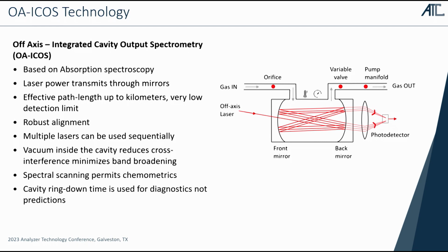We make these measurements at reduced pressure. We bring in low pressure to the analyzer, use orifices and a pump to maintain a very consistent low pressure in the gas cell. This helps sharpen the peaks, sharpens the bands. You don't suffer from as much band broadening. And then since we're collecting the spectrum, we can bring it into a chemometrics routine.